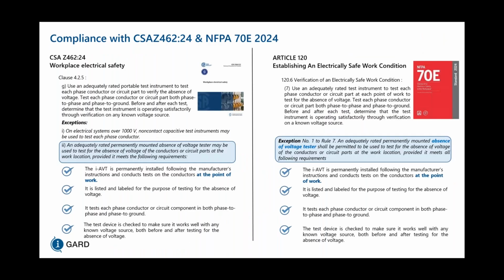In CSA Z462, which closely mirrors NFPA 70E but is the Canadian edition, they also provide this exception in clause 4.2.5, exception number 2, where an adequately rated permanently mounted absence of voltage tester may be used to test for absence of voltage on the conductors or circuit parts at the work location, provided it meets the following requirements. So the AVT has to be permanently installed following manufacturer's instructions and conducts tests on the conductors at the point of work. It is listed and labeled for the purpose of testing for the absence of voltage.